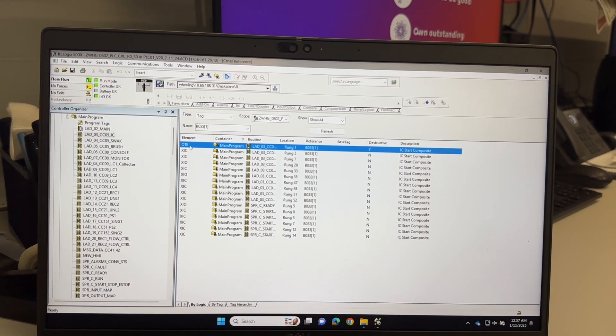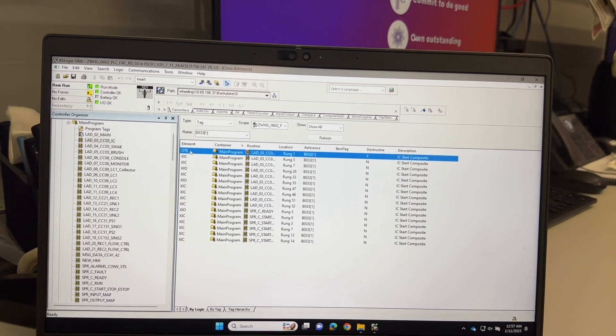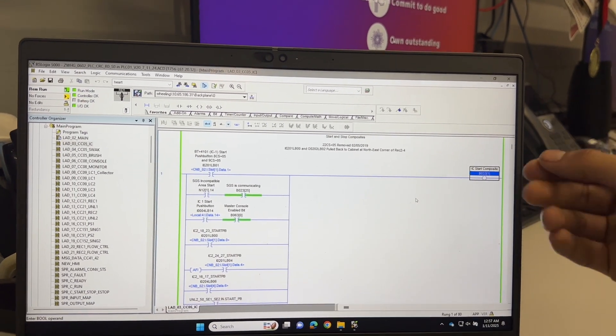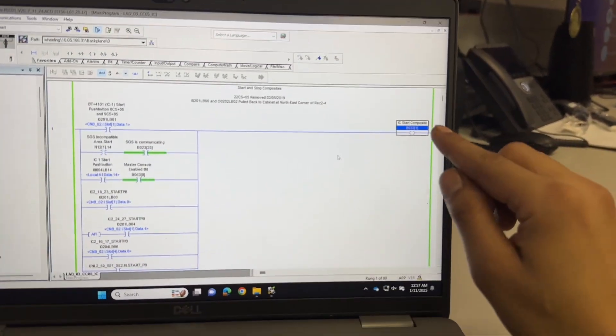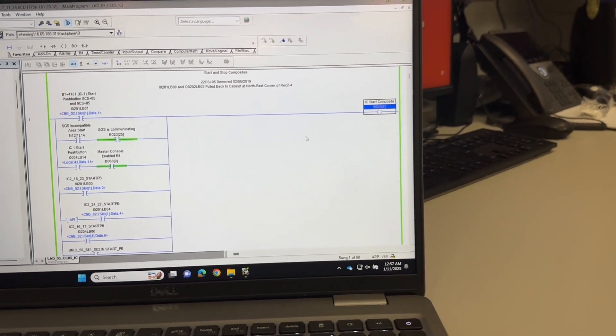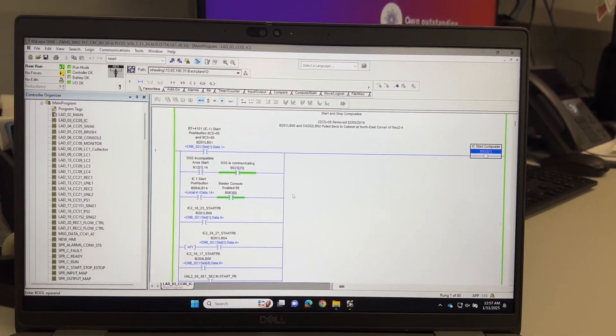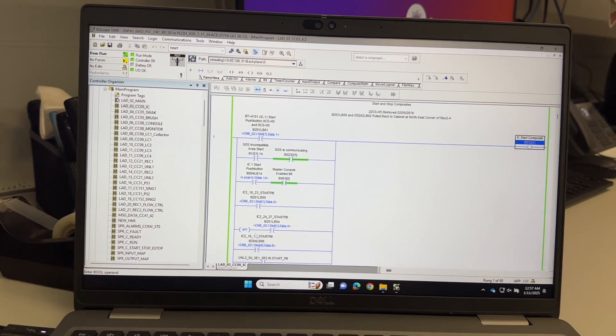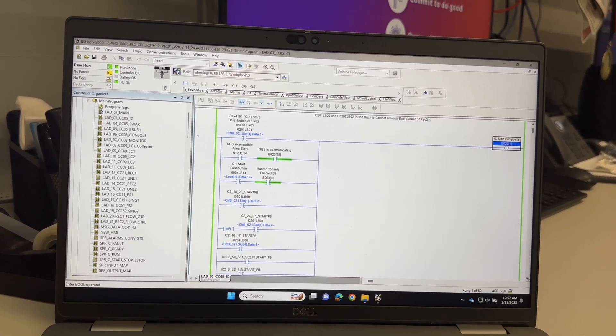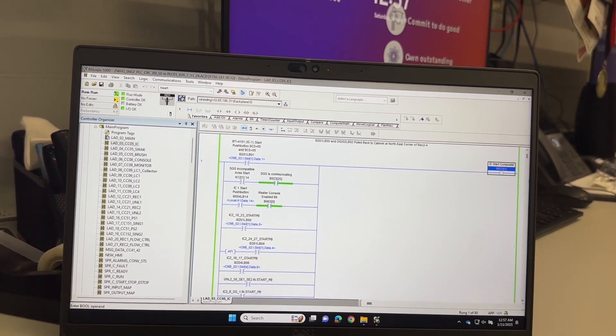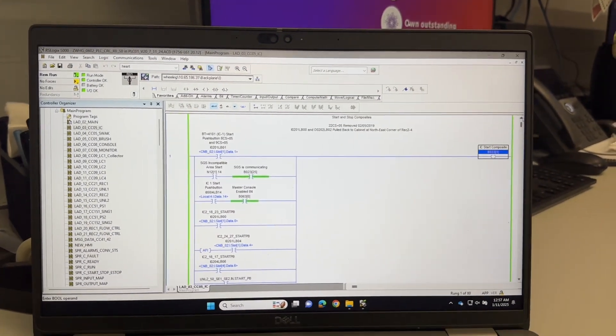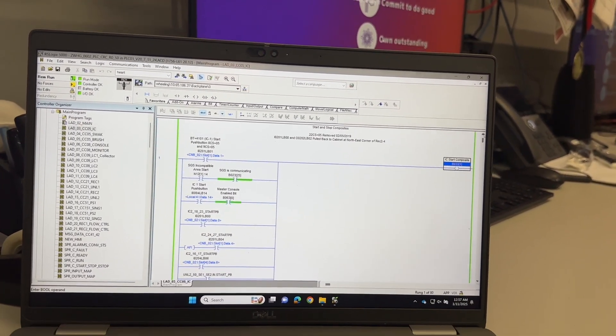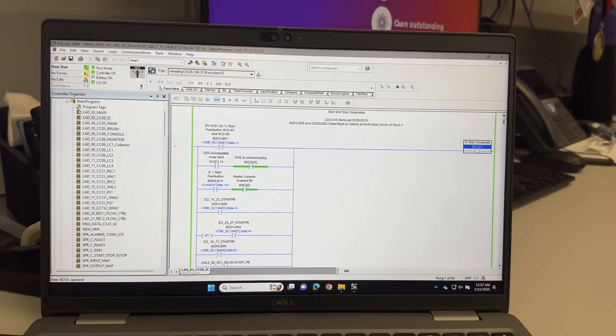The one that says yes is the important one, the one that's writing to this OTE or output. It's an internal output. So this is that start composite that we were just looking at. In order to turn that on, I would have to turn any of these bits on right here for a moment and then it would turn that machine on. That is the reason you would use the go to cross reference setting and I hope that helped out.